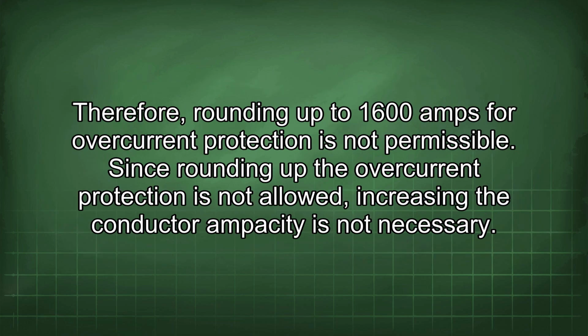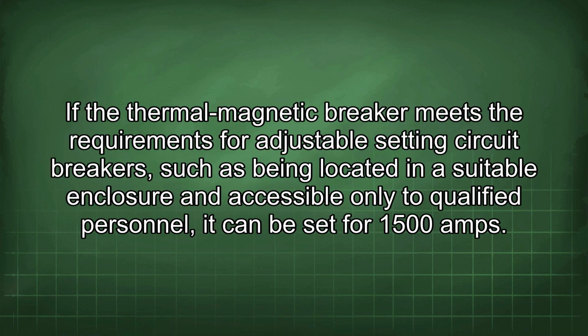Therefore, rounding up to 1600 amps for overcurrent protection is not permissible. Since rounding up the overcurrent protection is not allowed, increasing the conductor ampacity is not necessary. If the thermal-magnetic breaker meets the requirements for adjustable setting circuit breakers, such as being located in a suitable enclosure and accessible only to qualified personnel, it can be set for 1500 amps.